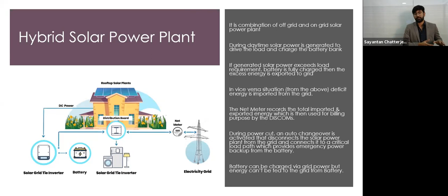Now the most important part: at the time of a power cut, this hybrid inverter will work as an off-grid one. It is already connected with a battery and will be islanded from the conventional grid. The battery will then run all critical loads, such as computers or lifts in an organization, or an ICU in a hospital. For that purpose, this hybrid plant is very useful. For major loads, you put a grid-connected power plant that sufficies your energy criteria and reduces your electricity bills, but at the time of a power cut, instead of using a diesel generator, you use the solar battery.